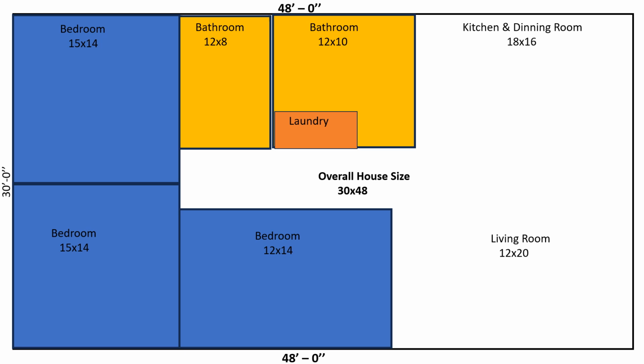When I first started out with Allied Mechanical back in '96, I'm sorry, '94, we looked at this, and back then it was 400 CFM per ton, and 400 square feet per ton if it was commercial with concrete floor, lay-in ceiling, or 500 square feet if it's a normal house with insulation.